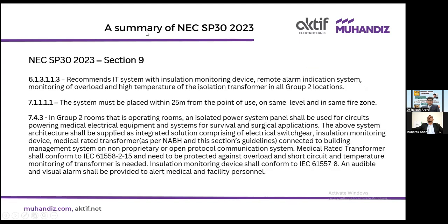Okay, now coming to the NEC SP30 2023. What I've observed in the standard is that around 30% of it talks about the IT system. Just to make some points, 6.1.3 recommends an IT system with an insulation monitoring device, remote alarm indication system, and monitoring of overload and high temperature of the isolation transformer in all group 2 locations. And 7.4.3 and 7.1.1 also mention things in much detail.